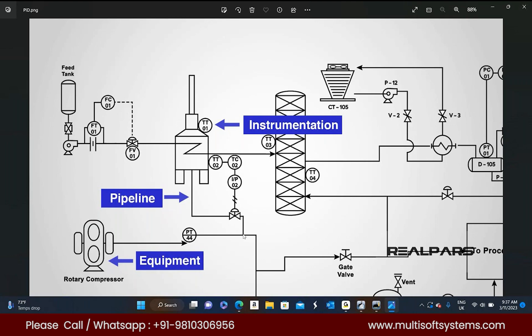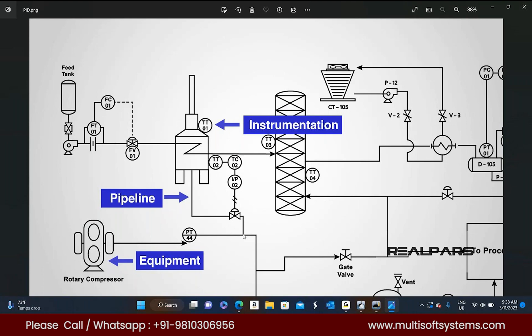To avoid that one, first of all we have to place breaks. Suppose if you don't want to pass sequence number, fluid code, insulation purpose - whatever you want, you can place that kind of break. If you want to stop all the properties at a time, that kind of break is also there. Individual break is there, as well as combo break is there. Combination of break - multiple properties it will stop.